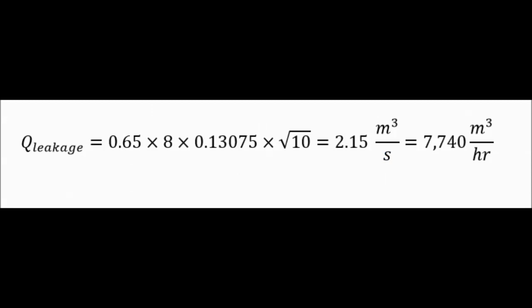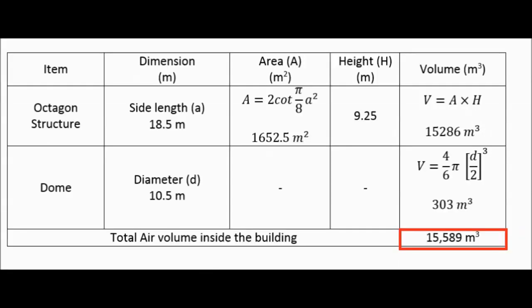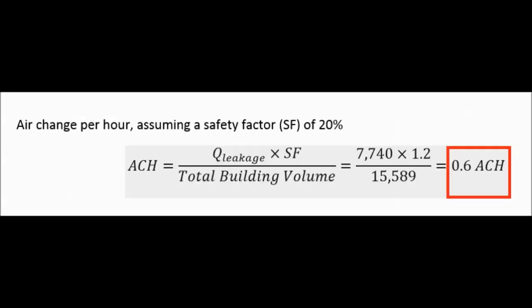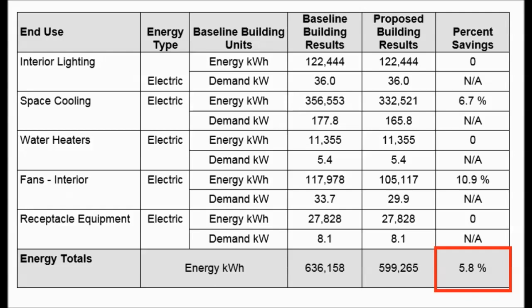The calculated infiltration rate was found to be 7,740 cubic meters per hour, and the mosque total volume is 15,589 cubic meters. Considering a safety factor of 20%, this gives an ACH value of 0.6. The total savings from using this ACH value on the building total energy consumption was found to be 5.8%.